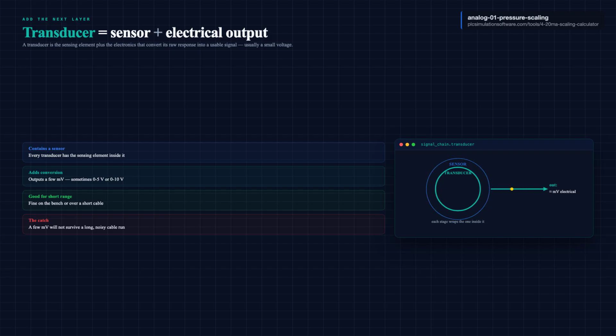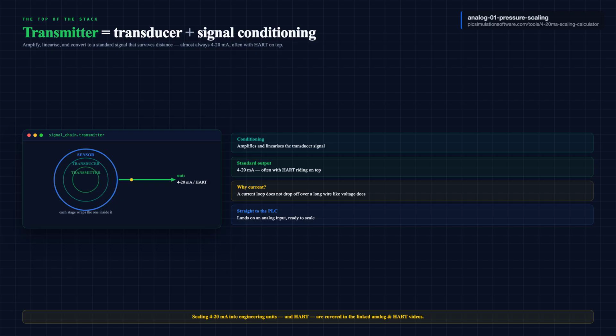Here is the top of the stack. A transmitter. A pressure transmitter is a transducer plus signal conditioning. It amplifies the signal, it linearizes it, and it converts it to a standard, transmittable output that travels over distance without falling apart. In industry, that output is almost always 4 to 20 milliamps, often with HART riding on top of it. Why current and not voltage? Because a current loop does not drop off over a long wire the way a voltage does. So the transmitter is a transducer packaged to send a robust, standardized signal straight into a PLC analog input. That is the difference between a transducer and a transmitter, the conditioning and the standard output. I cover scaling that 4 to 20 milliamp signal into real engineering units in the linked analog input videos. HART gets the linked HART explainer.